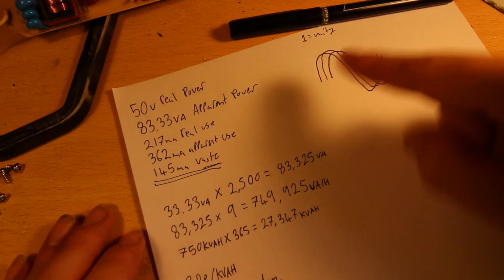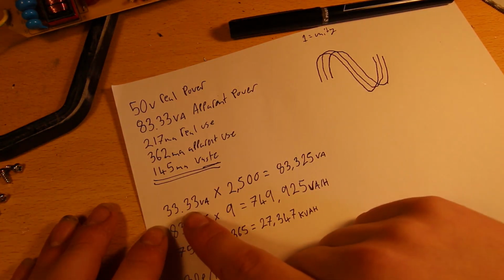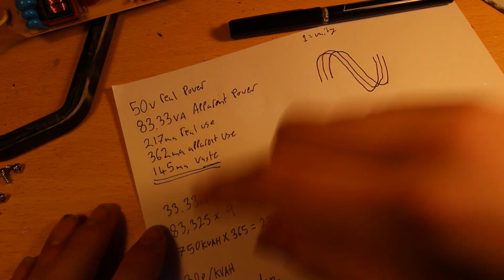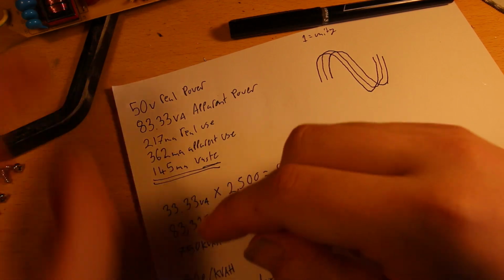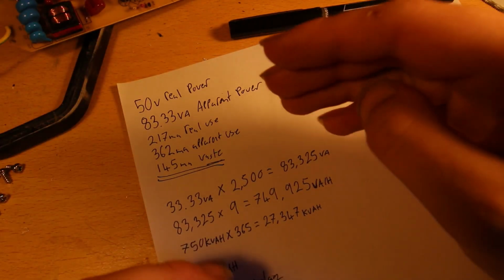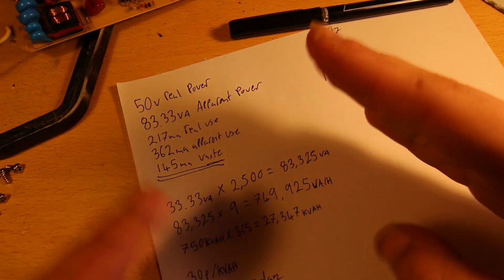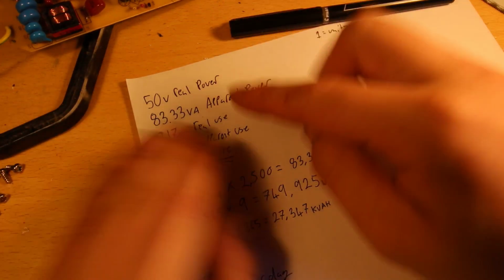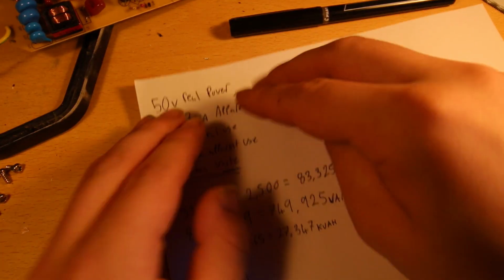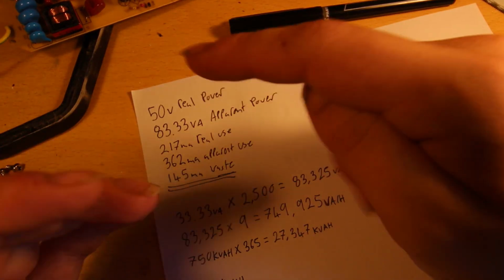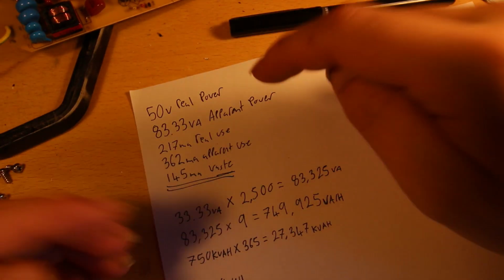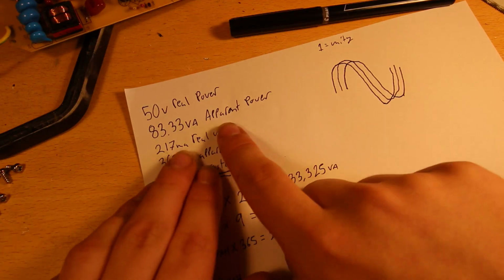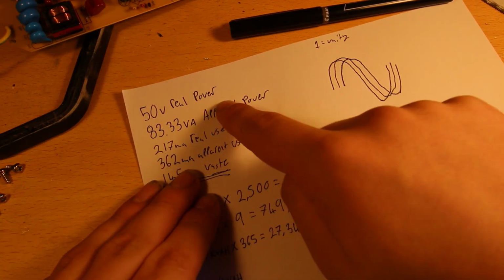That works out to 33.33 volt amp of wasted reactive power per light fixture. I should explain: as an individual domestic consumer, you only get billed for the real power consumption, not the apparent power usage. Commercial and industrial consumers, though, do get billed for both—they get billed for the apparent power, not just the real power.